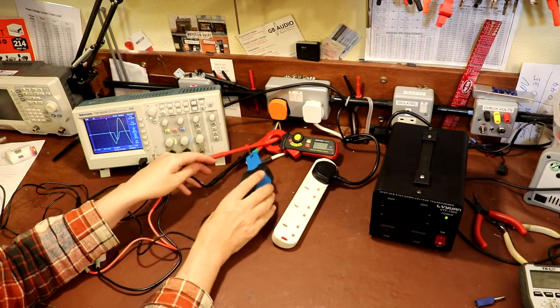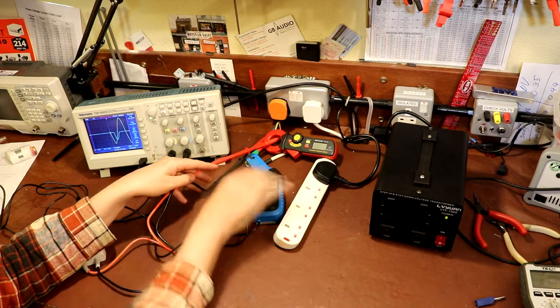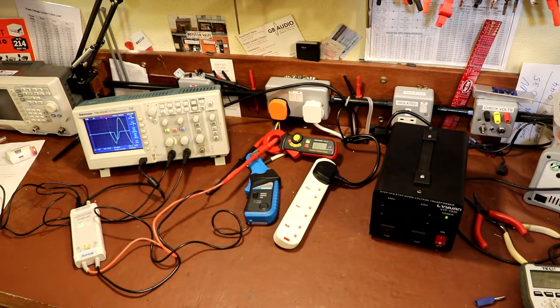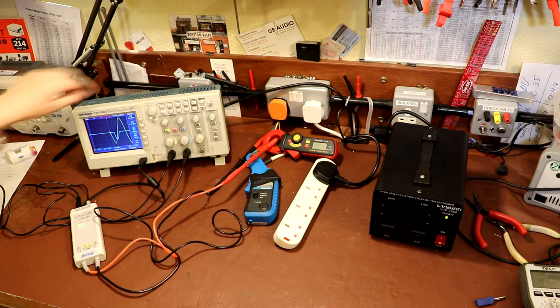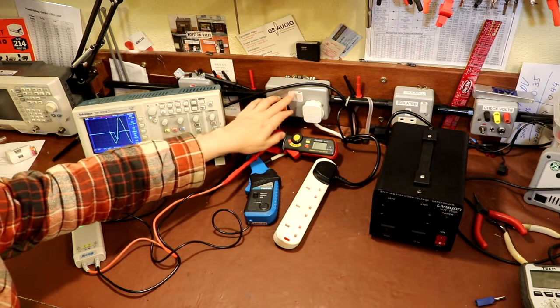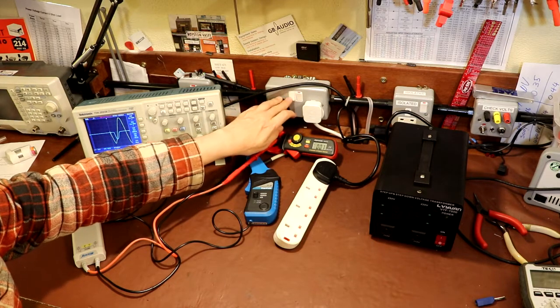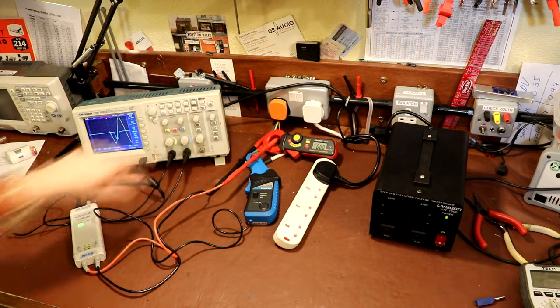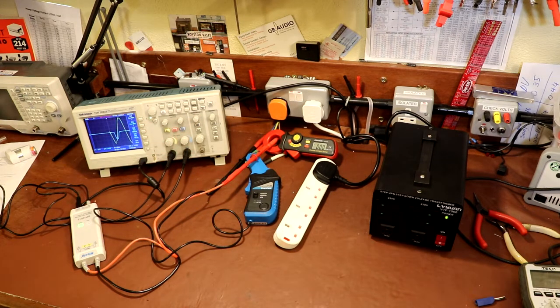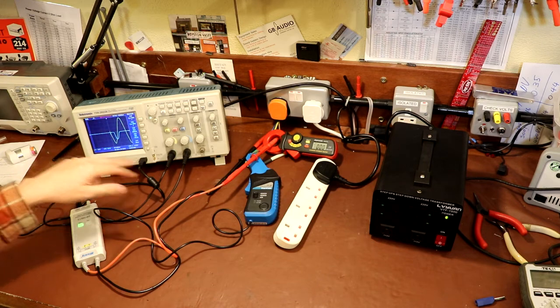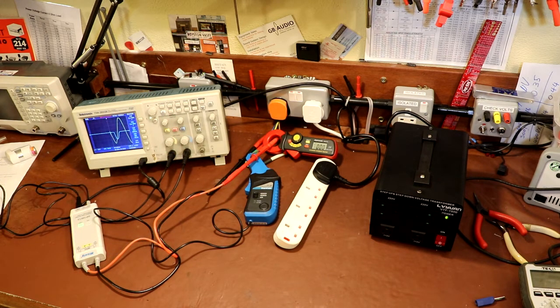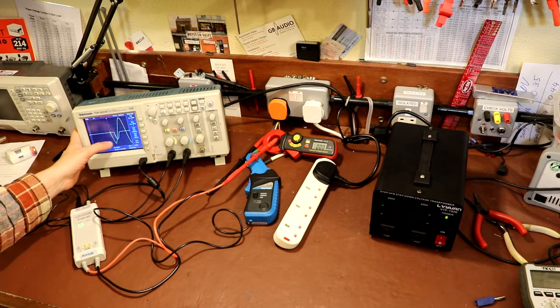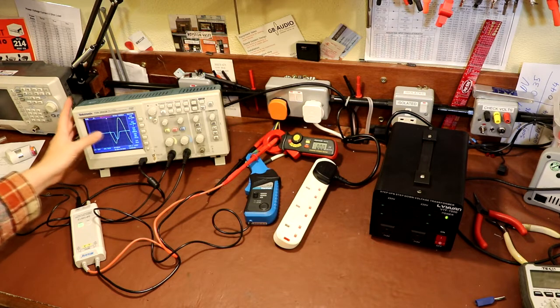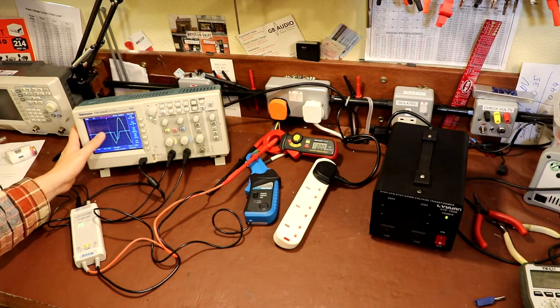And then on the incoming side of the transformer, on the primary side, I'm measuring the current using this clamp meter. All I've been doing is setting up the scope to trigger on the incoming mains when it detects some mains, and you've got to switch it on and off like this. You just keep switching it on and off, and using the scope in a single sequence, I've been capturing some waveforms. You've got to do it repeatedly because when you flick the switch on you don't quite know at what part of the mains cycle you are, so it's kind of pot luck.